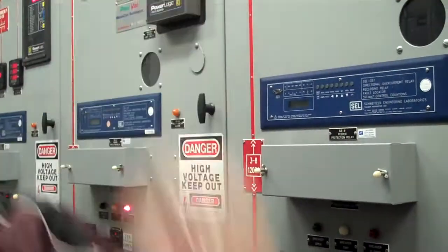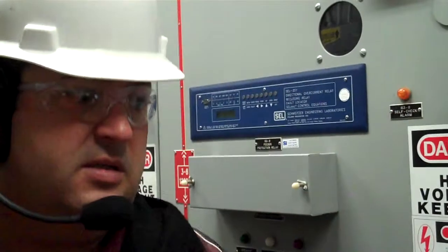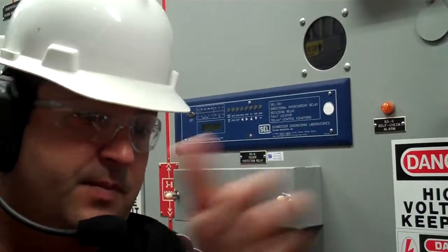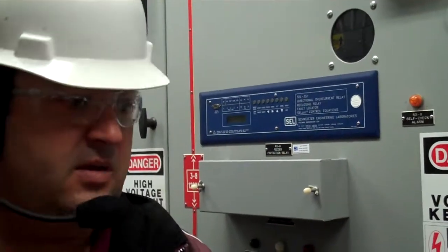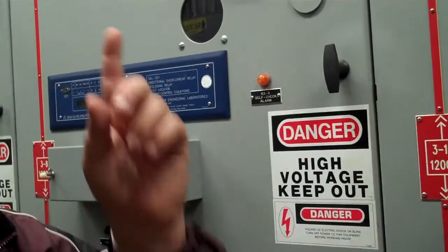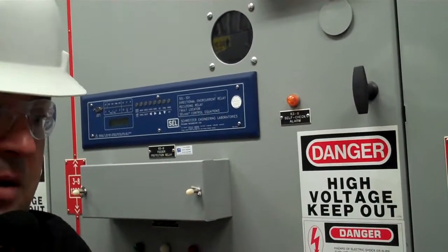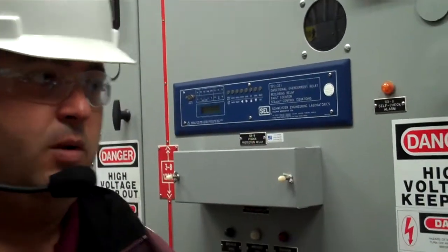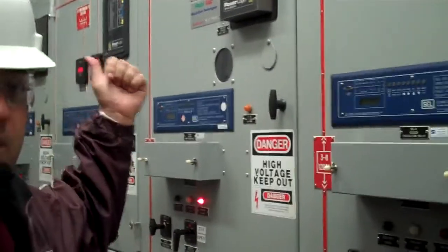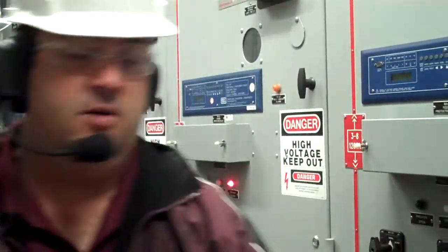We actually had an incident about 1.5 years ago where a breaker upstairs on a feeder had a faulted section of cable out by the building where Power Squared is at. The breaker mechanically failed. The relay worked in this case, but the mechanical latch bound up so the breaker didn't trip. We actually had a trip at the substation. So we probably could have had better coordination, where I tripped the main here instead of taking it all the way up to the transformers. We almost lost the 138 kV transformer.